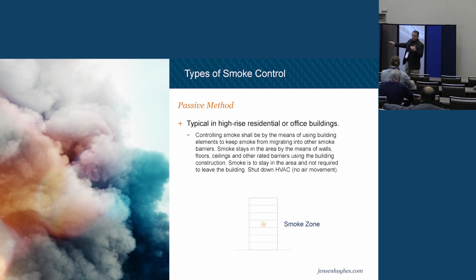We'll talk about tenant improvements and modifications and how that impacts the system in a minute. But anytime you're doing a renovation, and it can be as simple as adding a network drop, punching a hole in a wall needs to be thought about. If it's a corridor wall, that might be critical. A stairwell wall might be critical. So I may now be letting smoke or differential pressure air move in and out of a room that it was never intended to move in and out of. So you've got to think through all that, is kind of the point here.